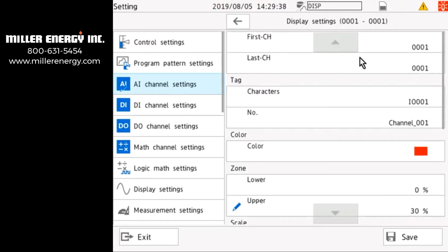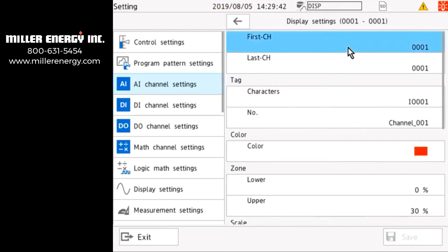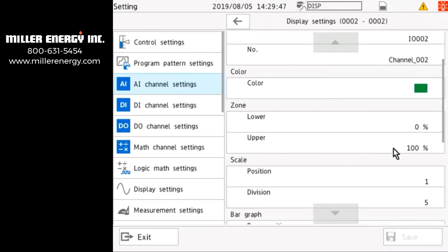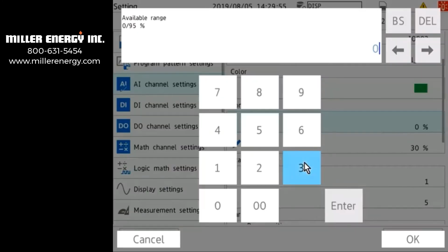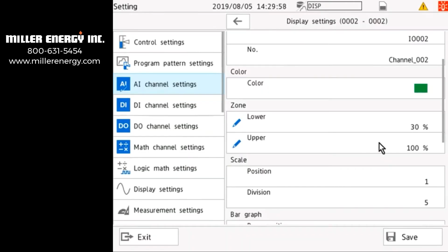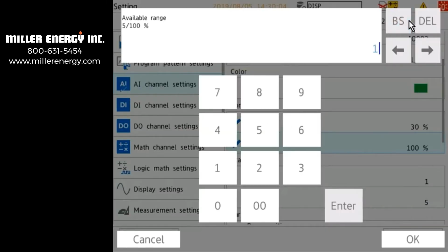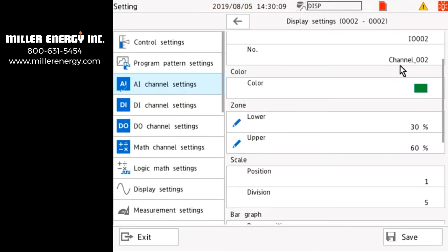Scroll up, confirm that this is the first thermocouple, save. Then we select the second thermocouple, which is the color green on the trend. Set this from 30 to 60% because the first input took up the display from 0 to 30%. So we'd go from 30 to 60% on here.